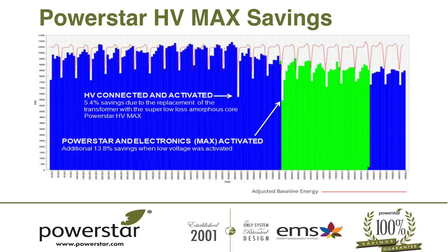This graph shows regression analysis IPMVP on a PowerStar HV Max installation. The red line is the regression analysis. At the changeover point from the old transformer to PowerStar HV Max, we saw a 5.4% energy saving just on the amorphous core technology. After running three weeks of verification, we then energised the voltage optimisation and got a further 13.8% energy saving — totalling over 19% energy saving on a PowerStar HV Max. Not unusual based on the typical voltages we see in Australia. This is in a large supermarket — and the average savings on HV gear are even higher than on LV gear.